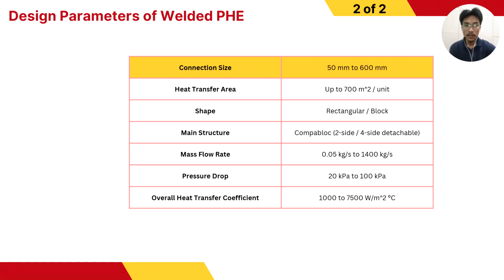And shape, it is rectangular or block. So the shape of a typical welded PHE resembles a block or rectangular in shape. But there are some welded PHEs that are cylindrical in shape. Next, main structure is a Compabloc, which is two-side or four-side detachable. So one of the main structures of a welded PHE is a Compabloc, which is rectangular in shape, and it can be detached by loosening or removing the side panel bolts. So there are two types. Two sides can be detached, and another type is four-side detachable. Four side panels can be detached.